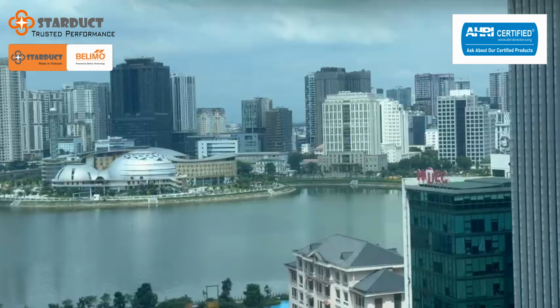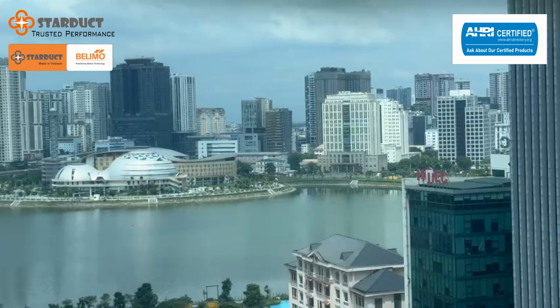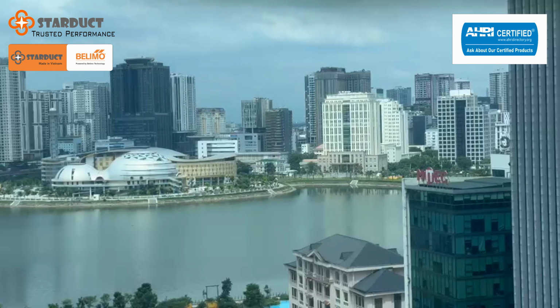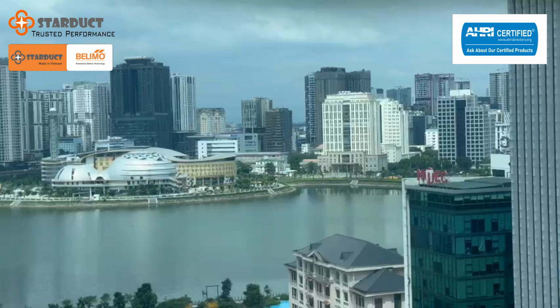This digital oversight provides a layer of protection that minimizes the need for constant manual checks just to catch catastrophic failures. If the sensor starts acting erratically, oscillating wildly, or just dies, the system is designed to flag that immediately. This allows for proactive diagnosis before a major flow inaccuracy develops and persists. So while you're focused on, say, gradual drift needing a 6-month check, the digital system offers a form of continuous, real-time validation of the sensor's basic operational health, confirming the input data for that K-factor calculation is at least plausible.